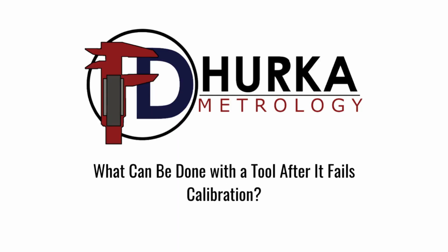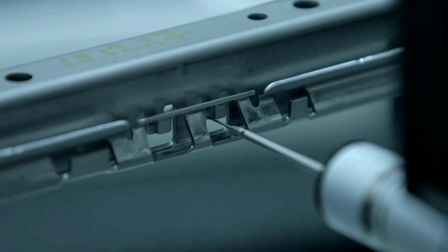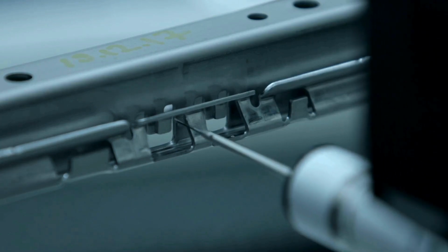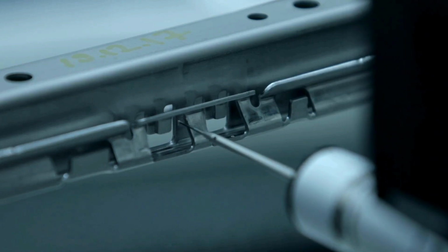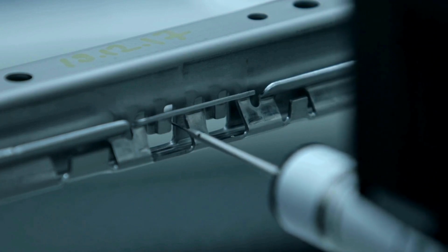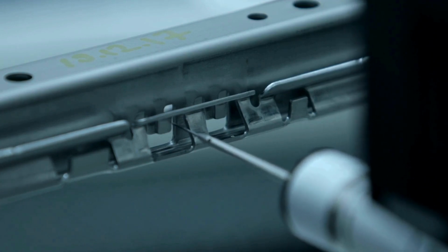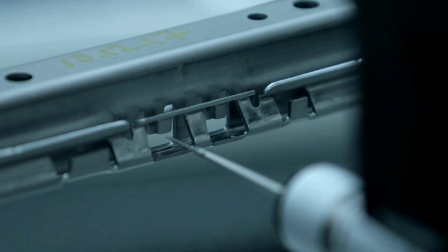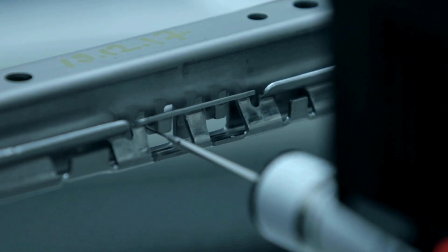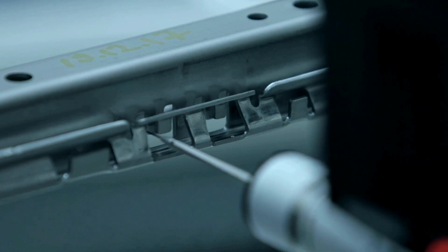What can be done with a tool after it fails calibration? Depending on the condition and the nature of the failure, it may be adjusted and recalibrated, repaired, evaluated further, or replaced. If it returns to service, the records should show that it was restored to acceptable limits.